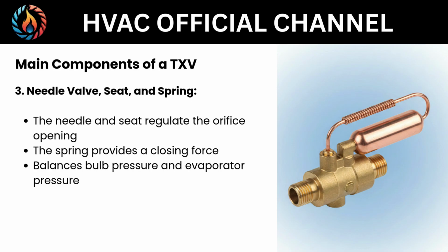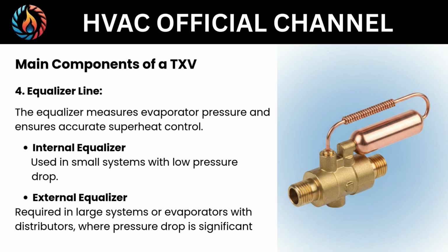3. Needle valve, seat and spring. The needle and seat regulate the orifice opening. The spring provides a closing force. Balances bulb pressure and evaporator pressure. 4. Equalizer line. The equalizer measures evaporator pressure and ensures accurate superheat control. Internal equalizer, used in small systems with low pressure drop. External equalizer, required in large systems or evaporators with distributors, where pressure drop is significant.